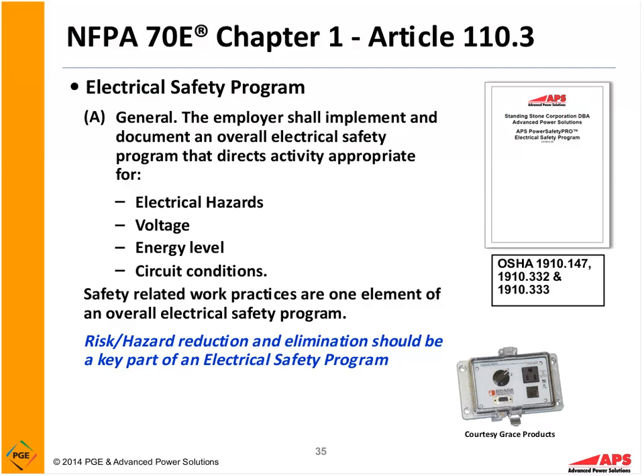And by the way, if you say you're following 70E, please read it carefully before you make a blanket statement. Fed OSHA and the state OSHA programs have not mandated 70E. It's absolutely important for you to know 70E to try and comply with it, but there may be some areas where you want to do something a little different than what exactly 70E calls for and still achieve the same results. So when we look at a safety program, risk and hazard reduction and elimination should be a key part. In other words, it's not about just putting the PPE, the personal protective equipment, on. It's about how do we avoid it.